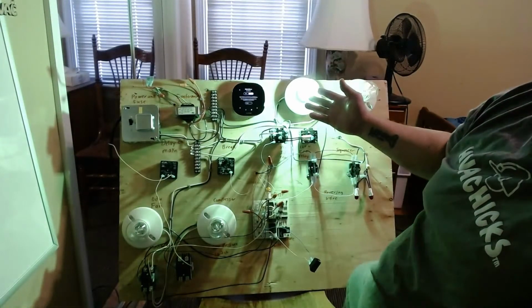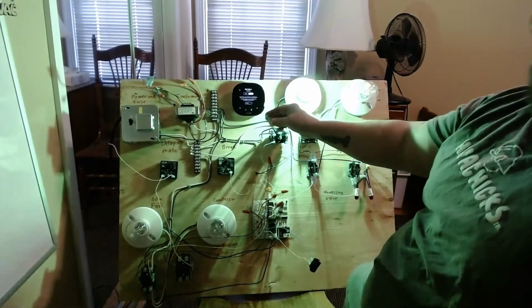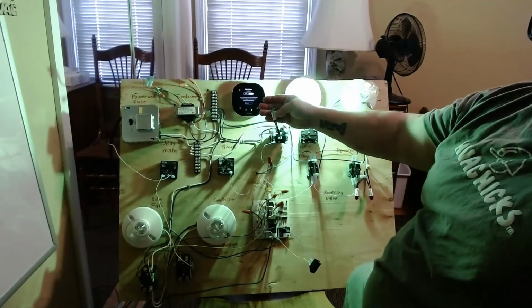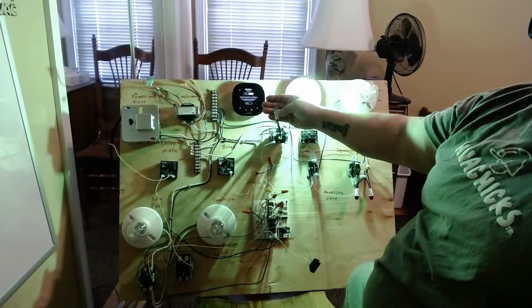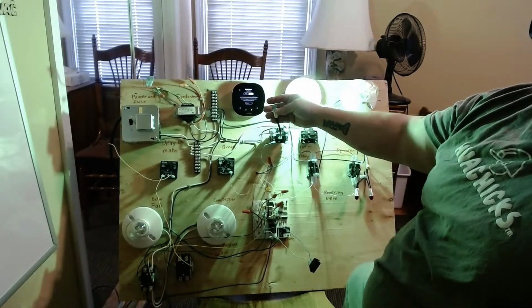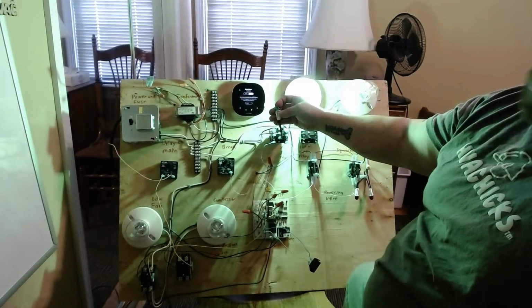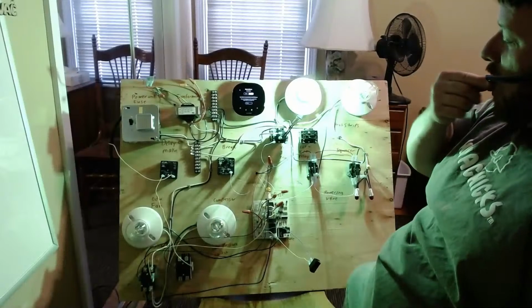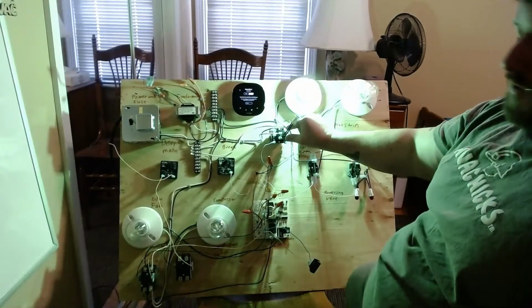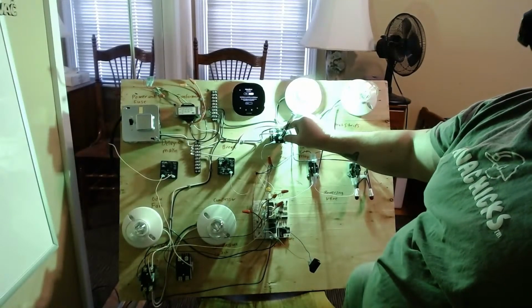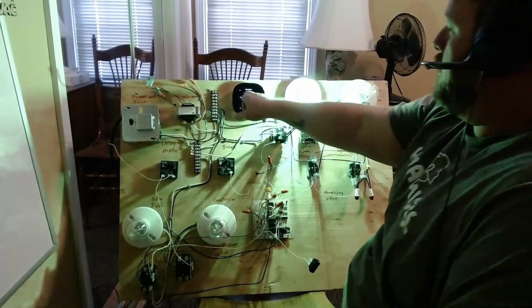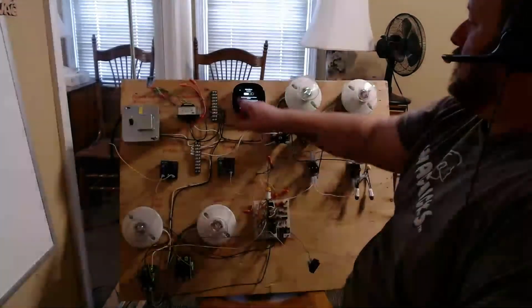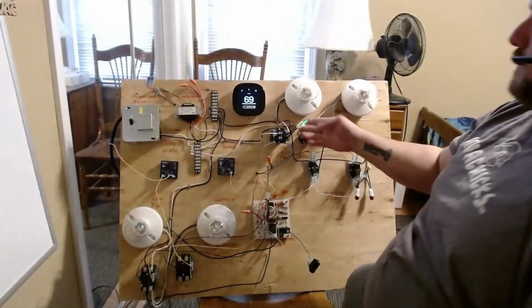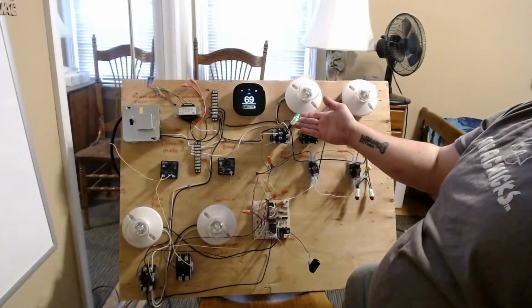You can see our fan is lit. Relay is on. But if you notice right here, this light is dead, right? Because that means it's de-energized, so there's no more voltage going to this. I could essentially pull this off, lick my fingers, and stick it across there and not get shocked. I would not get hurt. Notice the fan went off, light came back on.